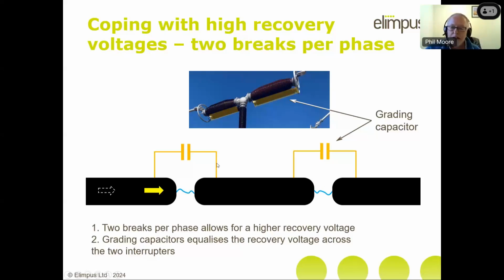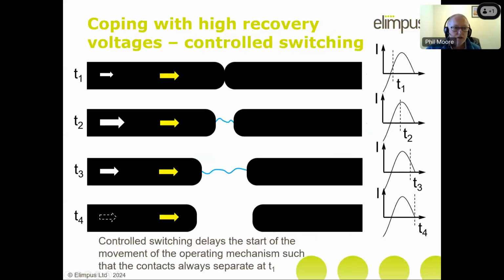And the next thing you can do to stop the arc reappearing is to use what's called controlled switching, and you've already seen controlled switching. This was what I showed you earlier. This is where you arrange for the contacts to part a couple of milliseconds or so after the penultimate zero crossing, which means that for the majority of the current, the arc is burning, and then it gets to the T4 point where the arc goes out, and the contacts are now far apart. That's the ideal state to be in, because if you don't control that operation, the point at which the contacts separate is essentially random.